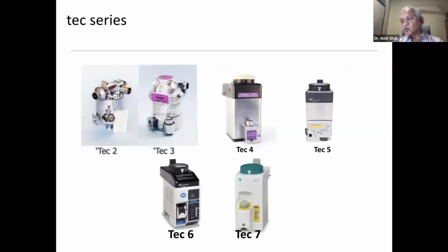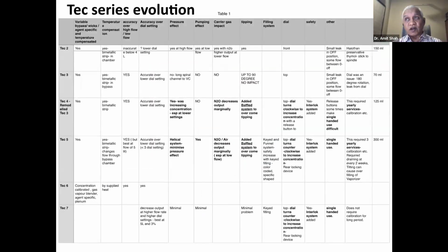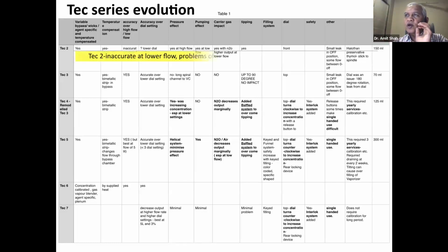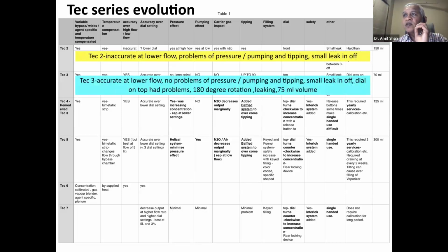So the Tec series is one which has been used since a very long time, 2, 3, 4, 5, 6, 7. 7 is the current one. I'll briefly take you through it; there is a very good Tec series evolution paper, and there is a very good table there. You can go through it. So Tec 2 had inaccurate flow, okay? And there was a problem of back pressure, pumping and tipping, and it was leaking in the off position. Tec 3 was better at lower flow. The 2 was inaccurate at lower flow.